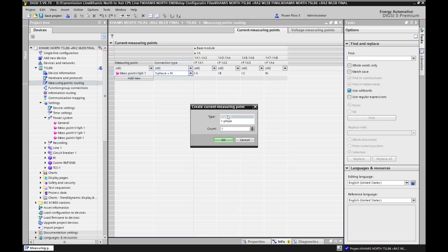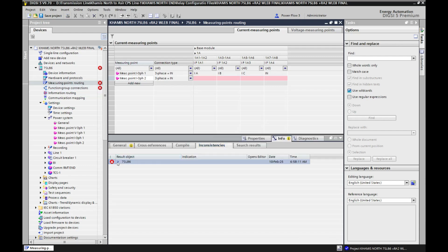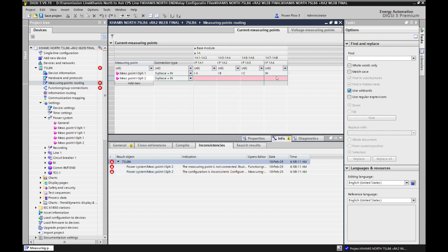I click three phase — single or three phase — which measuring point we need to add. For example, I want to add a three phase count. How many interfaces? We need to add only one, so we select one and click OK. Now an error appears because a three phase measuring point already exists — adding another three phase will cause an error. We will see what error is actually coming. If we go to inconsistencies, we can see: configuration is inconsistent — configure the measuring point to the terminals properly.